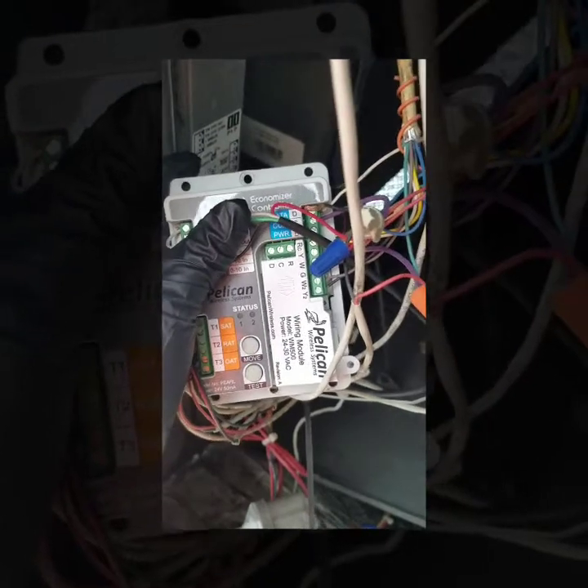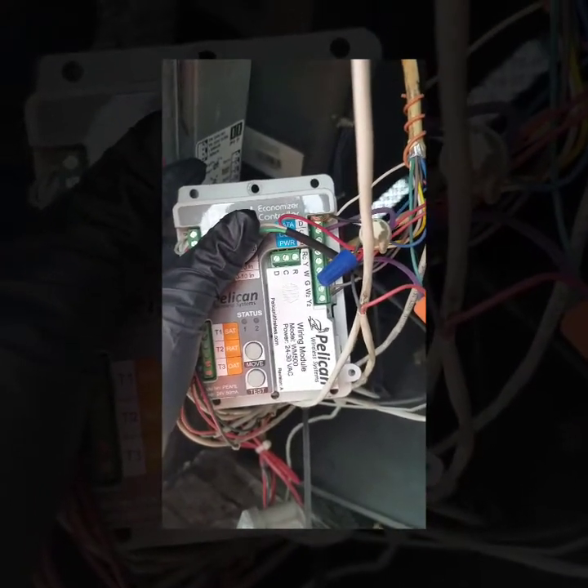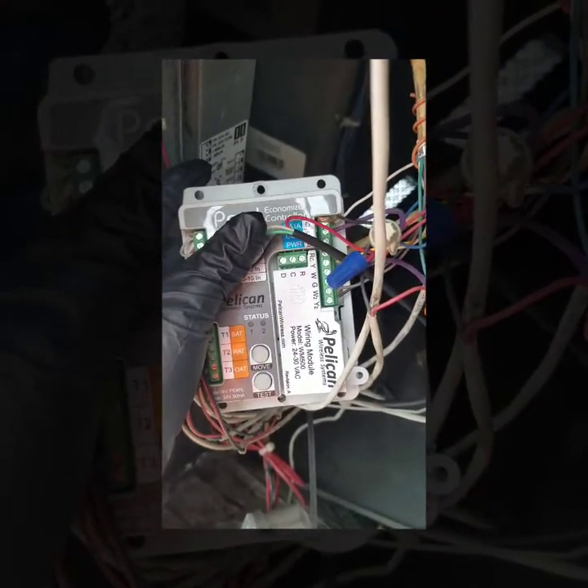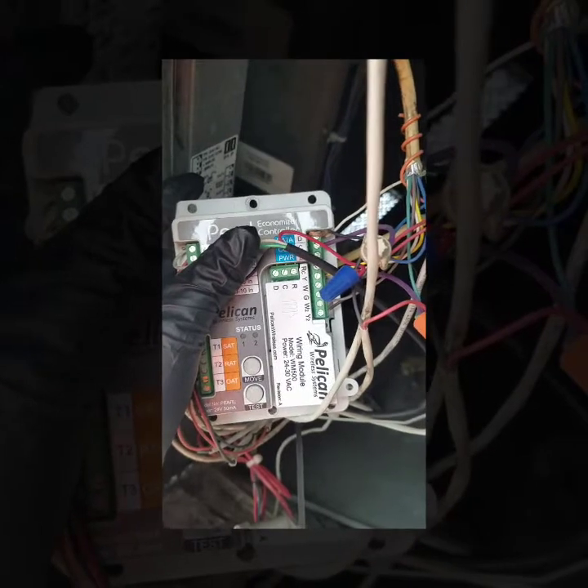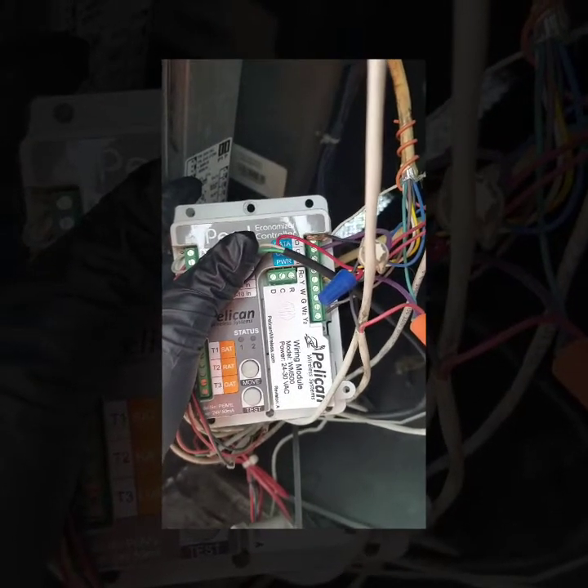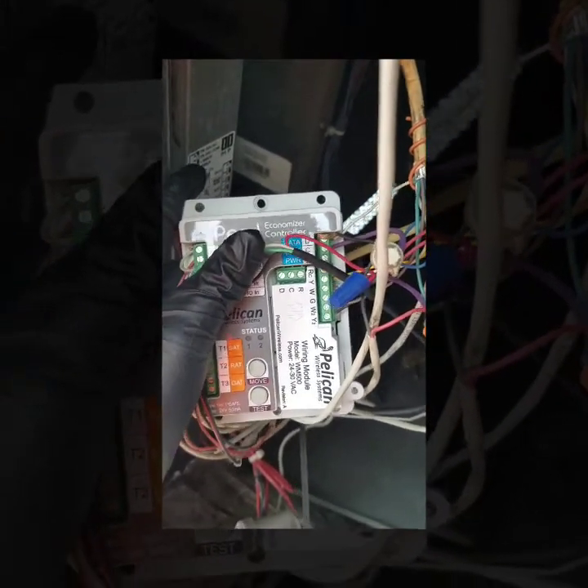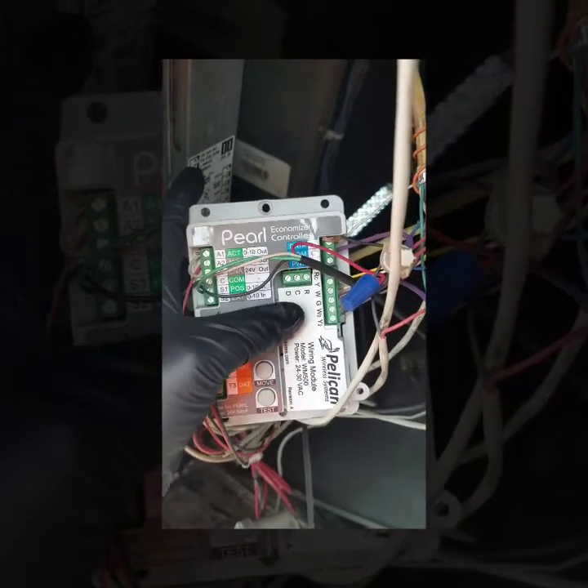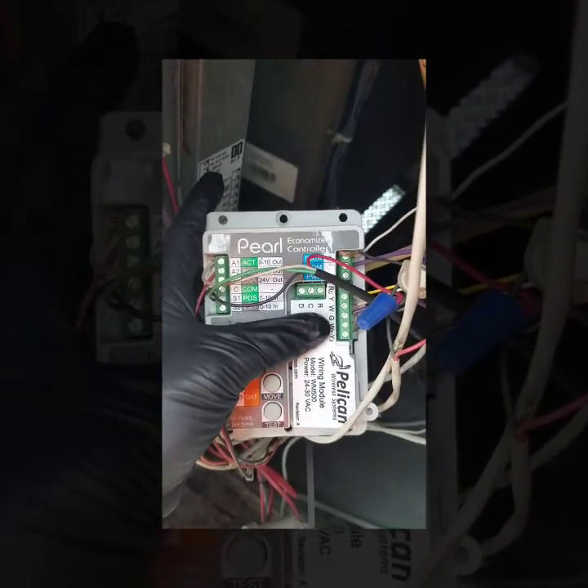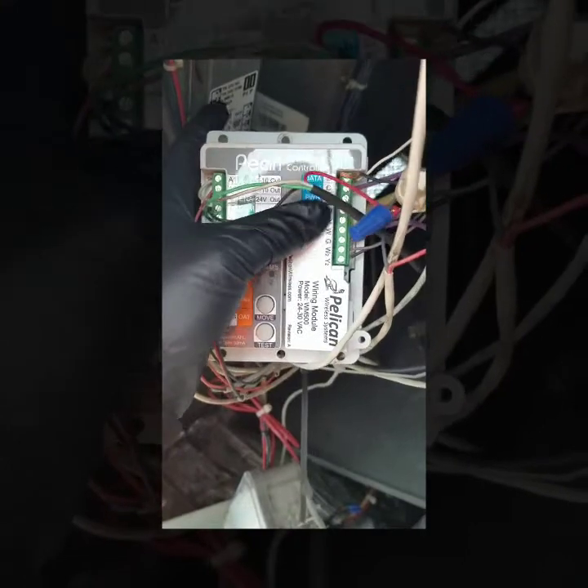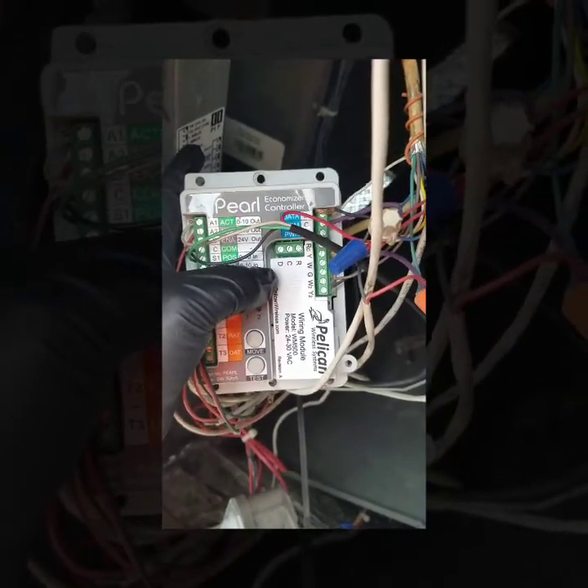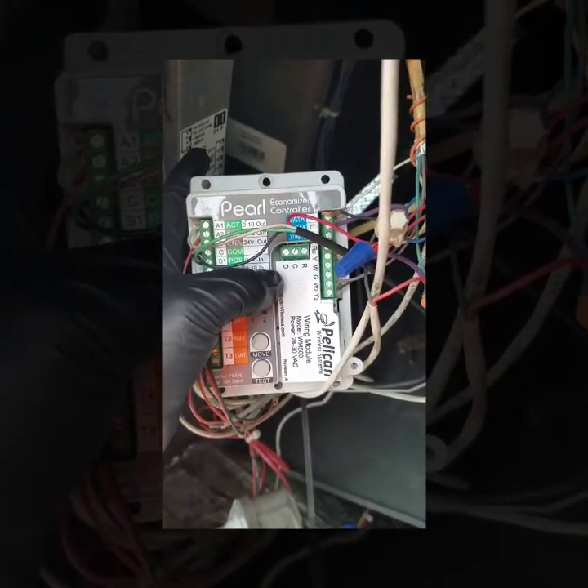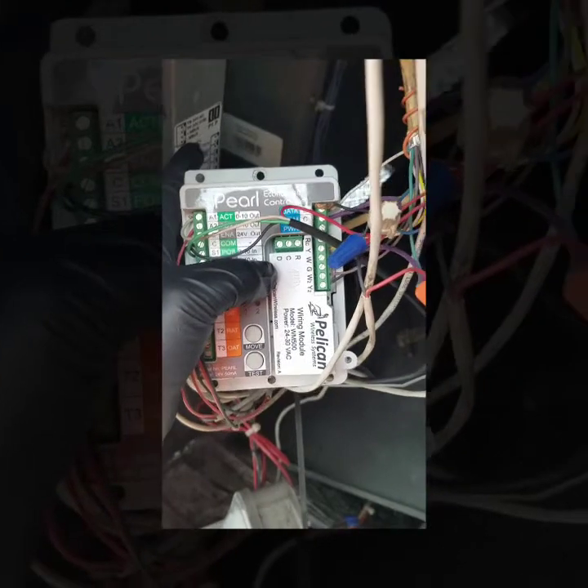So I just removed this from the panel. If you are running into issues with one of these Pelicans, leave a comment down below. I might be able to answer it. I've done quite a few of these, pretty much in all the different applications you can do. But another thing to look for is this R, C, and D. Make sure all these screws are tight. It's something easy to miss, but I've seen it overlooked multiple times. You get a lot of communication issues and stuff just won't be acting correctly.